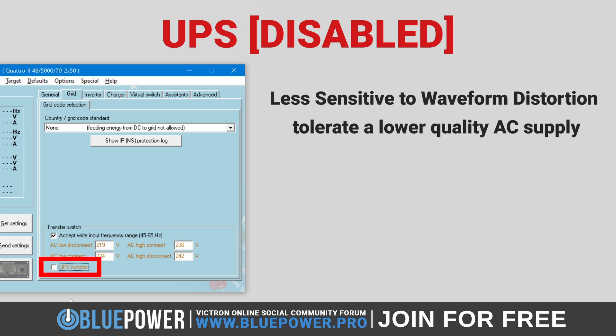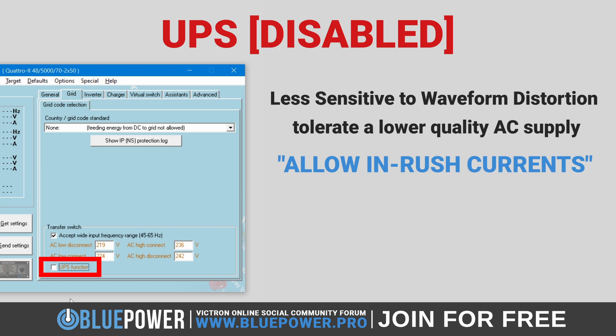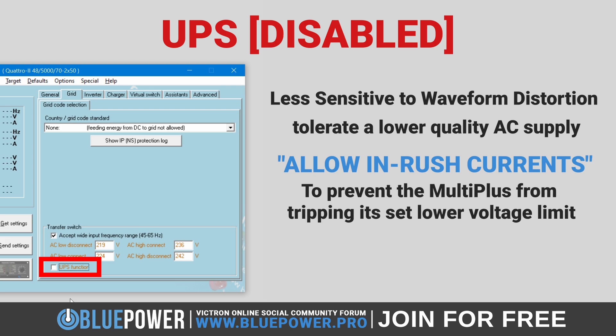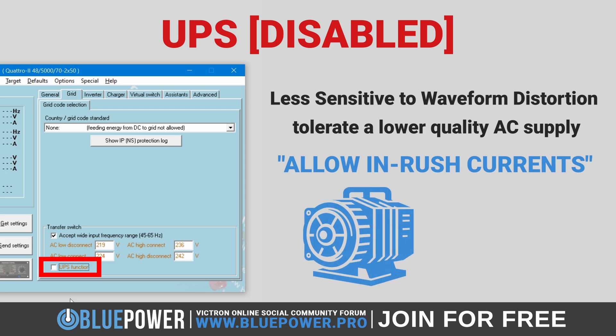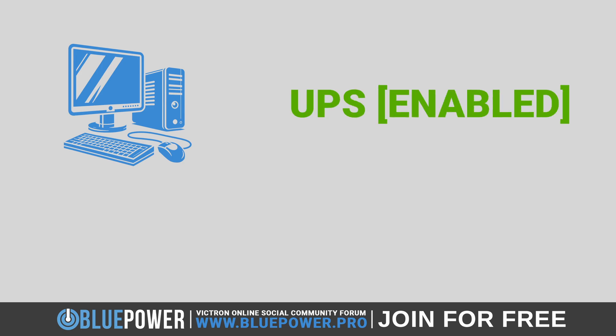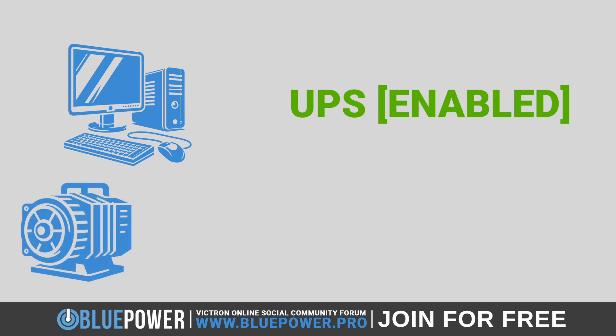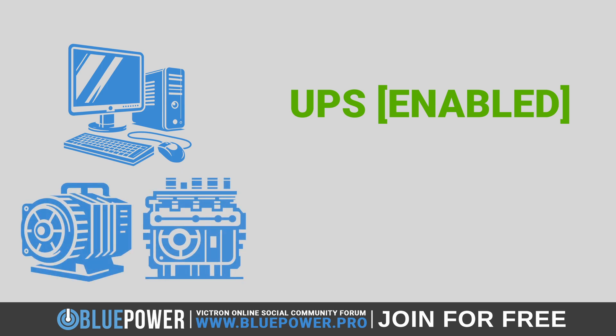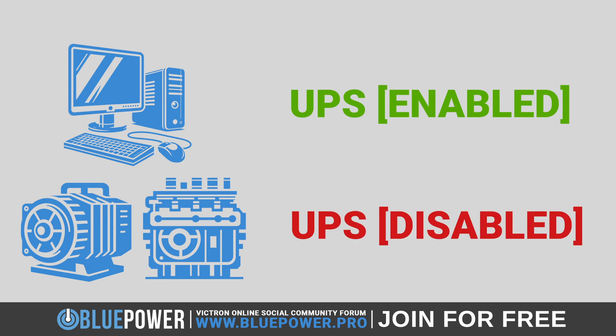Note that in previous software versions, deselecting this function activated a feature called Allow Inrush Currents, but now it will automatically enable inrush without the need to additionally activate it. This inrush current feature is designed to prevent the MultiPlus from tripping its set lower voltage limit when heavy startup loads are encountered, and is particularly useful for starting heavy loads that require a significant amount of current at startup, such as motors or compressors. Therefore, if your priority is to protect sensitive electronics and ensure they are always supplied with a high-quality waveform, you would keep the UPS function selected. Conversely, if you are using a generator that produces a less stable waveform, or if you need to start heavy loads that cause inrush currents, you would deselect this function to allow the inverter to handle these situations without disconnecting from the AC supply.